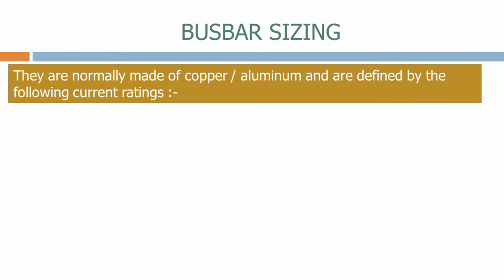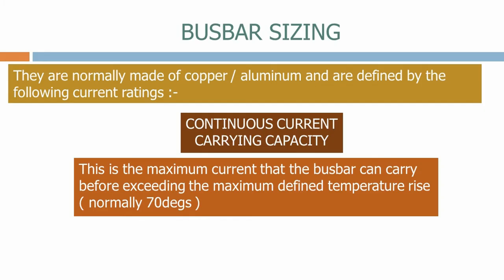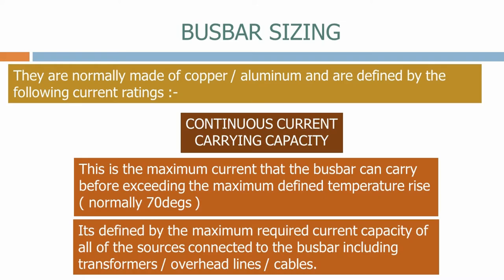They are normally made of copper or aluminium and are defined by the following current ratings. The continuous current carrying capacity is the maximum current that the busbar can carry before exceeding the maximum defined temperature rise, normally set at 70 degrees Celsius. It's defined by the maximum required current carrying capacity of all of the sources connected to the busbar, including transformers, overhead lines and cables. Most busbars on the electrical system range in capacity from 100 amps all the way through to 4000 amps.